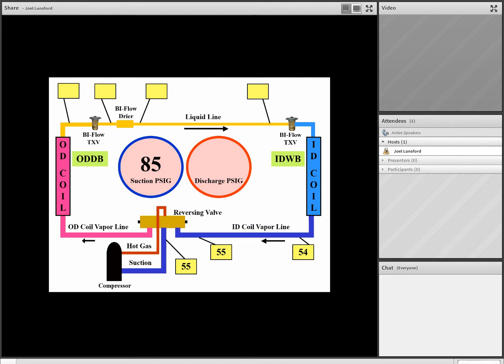So at 24 degree saturation temperature off the chart, remember 85 psig suction pressure, we convert that to temperature, and that equates to 24 degrees. So the temperature leaving the cold coil in the cooling mode on the indoor coil is 54 degrees. The difference between 54 and 24 is about 30 degrees of superheat again. And we found out earlier, and we refreshed our memory earlier, that 10 to 15 is normal, but we have a high superheat value. So a high superheat always means the cold coil is starved. And so again, in this 410A example, we have a starved cold coil.